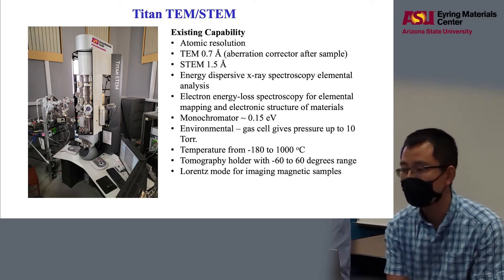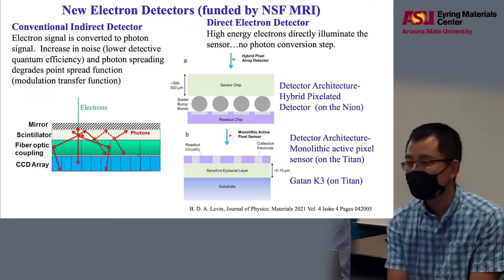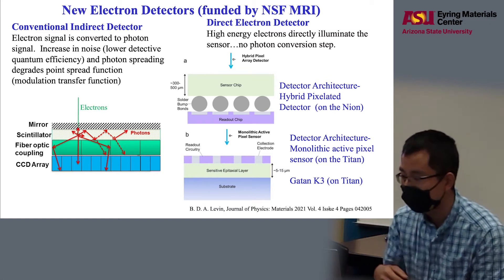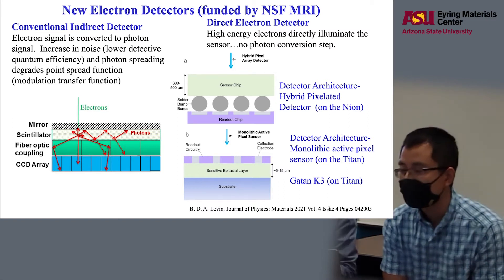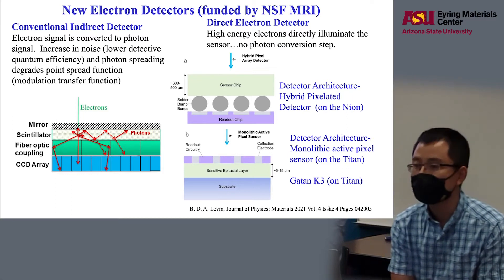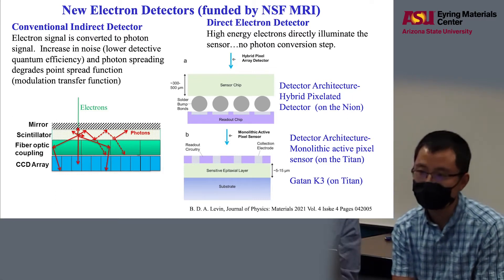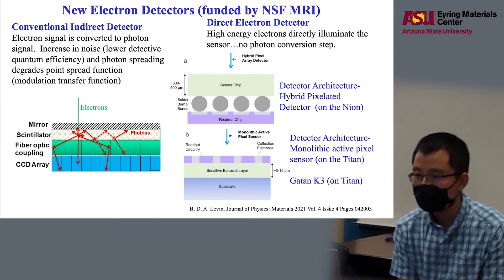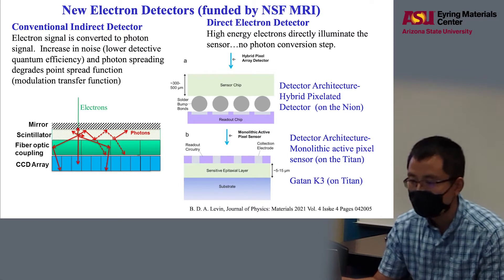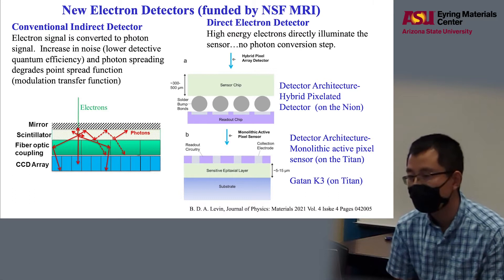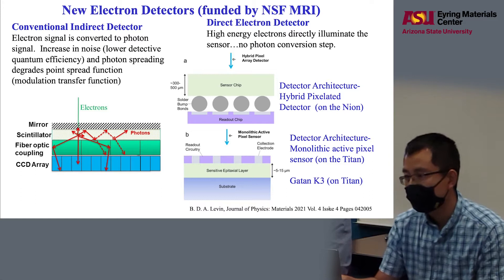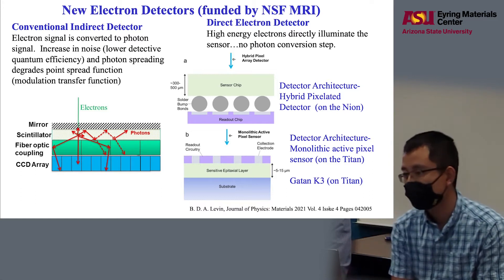It also has Lorentz mode for imaging magnetic materials. The new detector, which is funded by an NSF proposal led by Peter — I will briefly review the improvement of the new detector. For a conventional detector, the electron signal is converted first to a photon signal, and during the conversion process, there is some reflection in the scintillator layer, which will degrade the spatial resolution. With the new direct electron detector, the spatial resolution can be greatly enhanced.